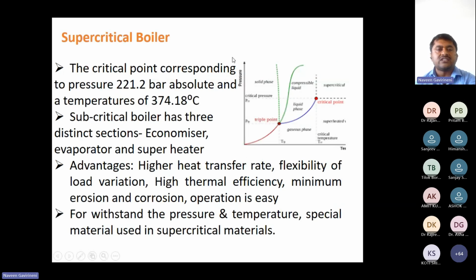So this is the supercritical concept. The supercritical point is 221 bar and 374 degrees centigrade. After this point, the water is directly converted into steam that will be used in the turbine. In a supercritical boiler there is no drum. There is one small vessel, meant for partial load bearing. While subcritical boilers all have a drum, because steam needs some time to segregate from the feed water in the drum.